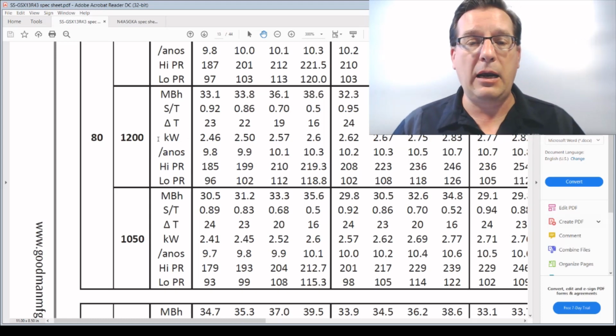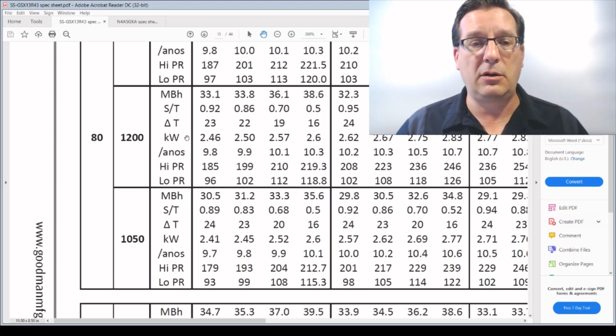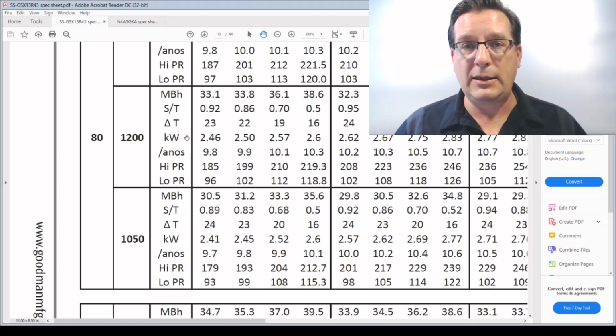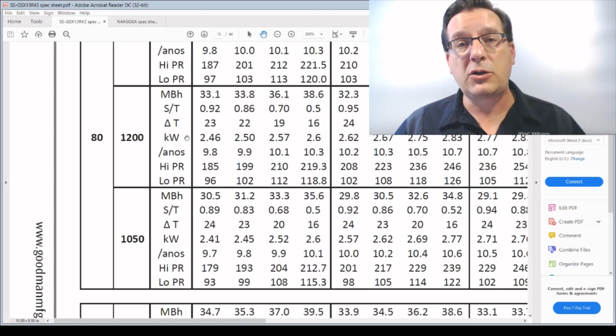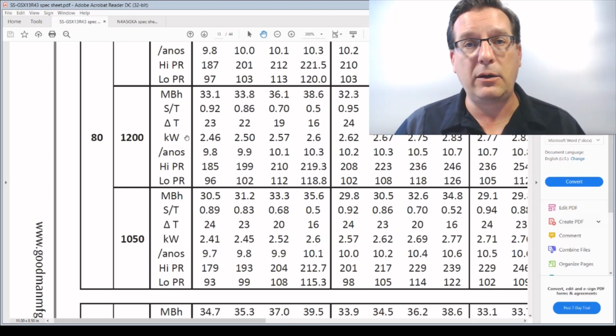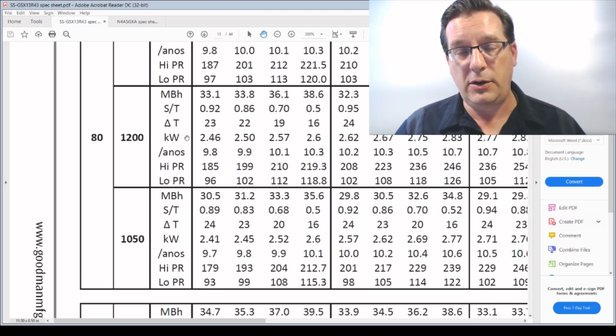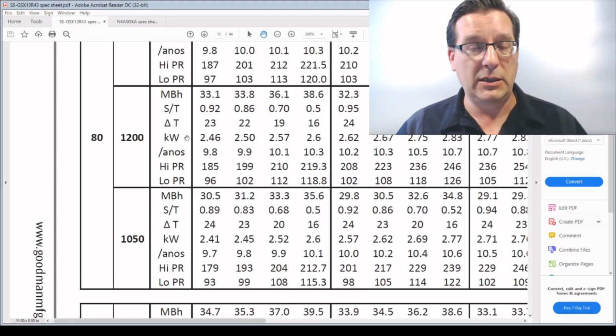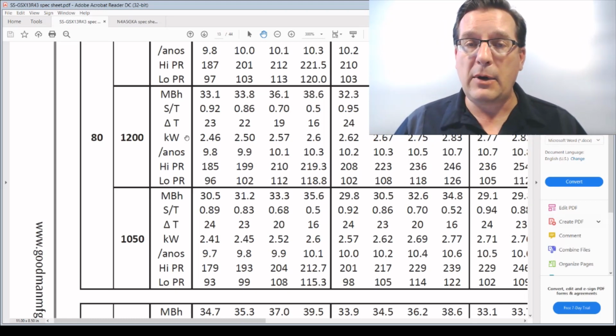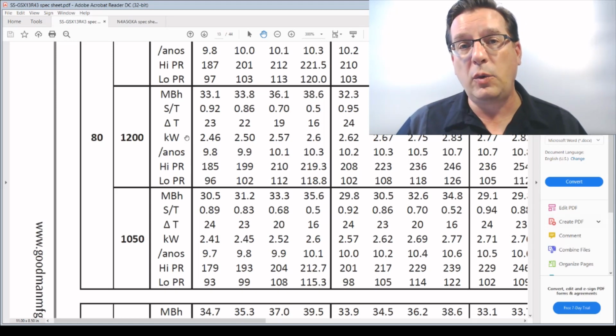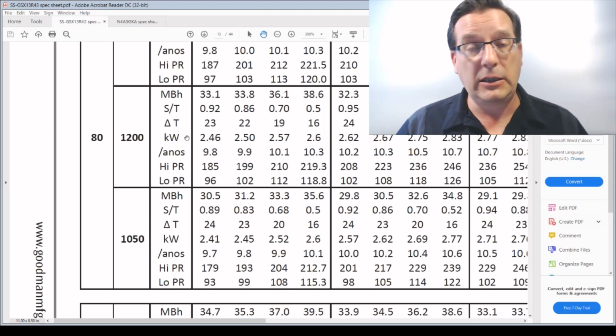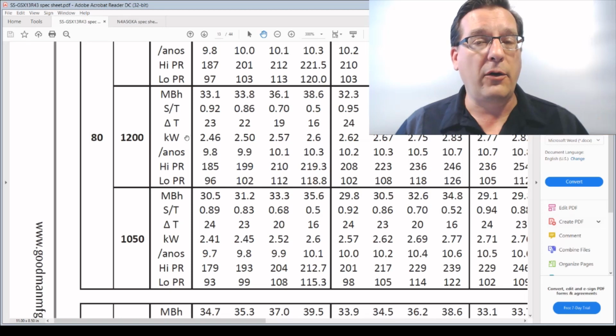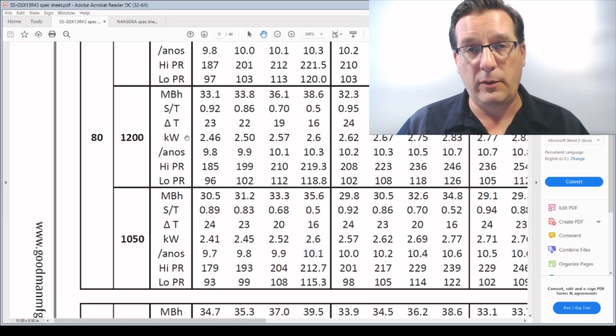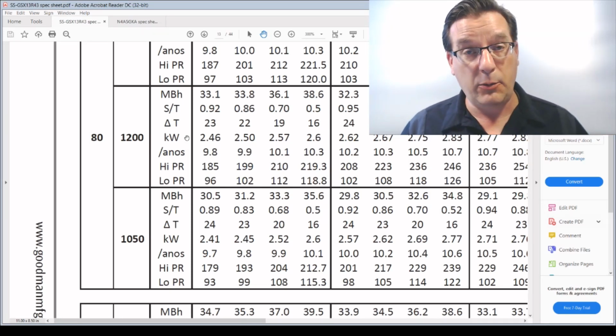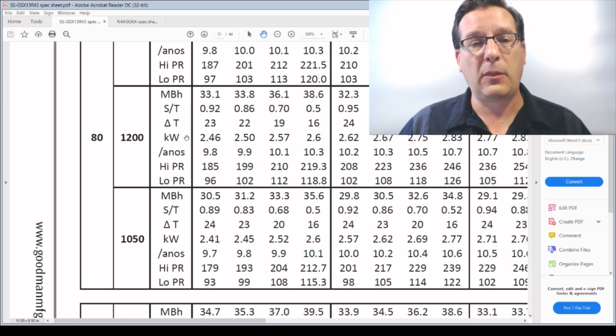Next one given is kW. This is an electrical symbol meaning kilowatts. How many watts of electricity are consumed by the condensing unit when it is operating under these conditions and producing this level of performance? The amount of electricity consumed by any air conditioner will change based on how many BTU it's removing and other factors that affect the performance, such as outdoor temperature, indoor temperature, and wet bulb temperature.